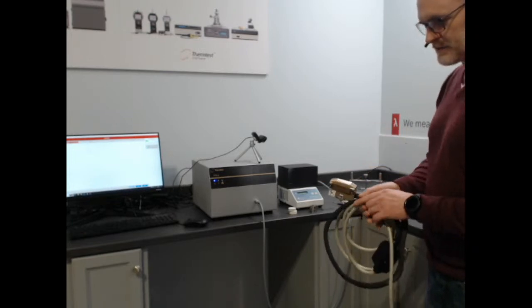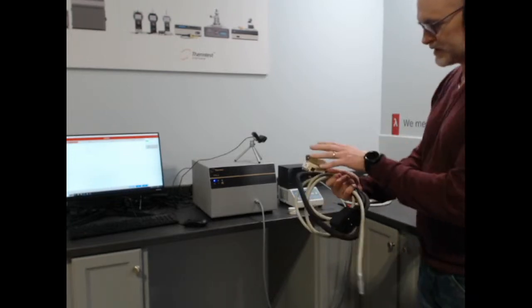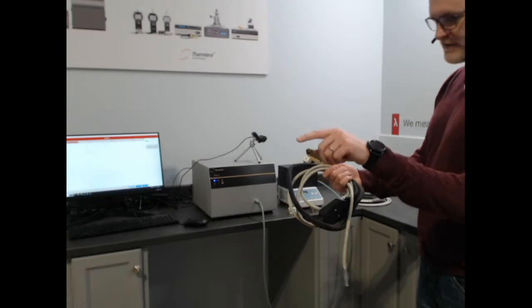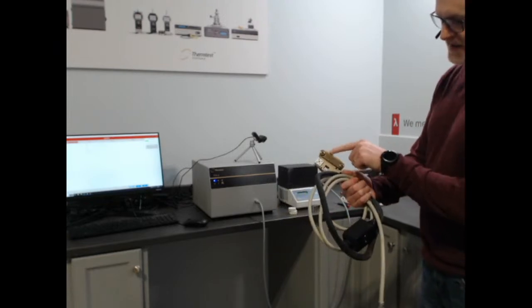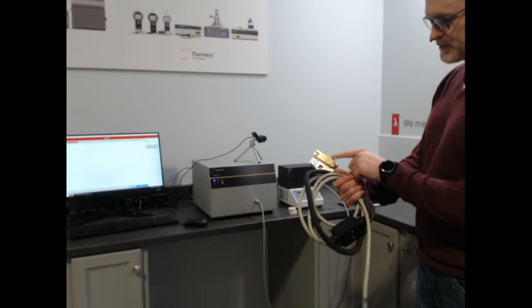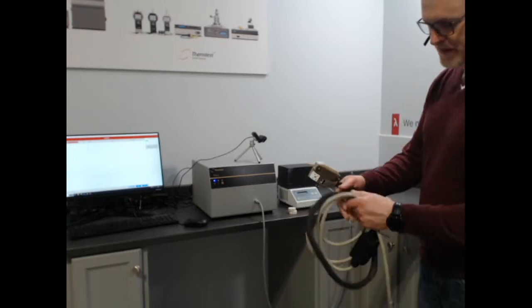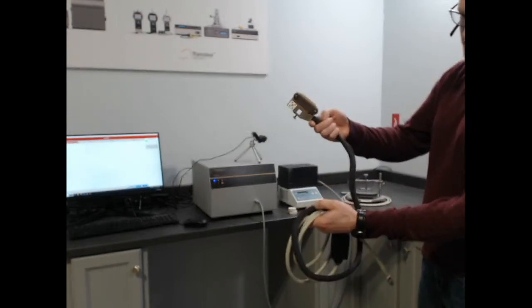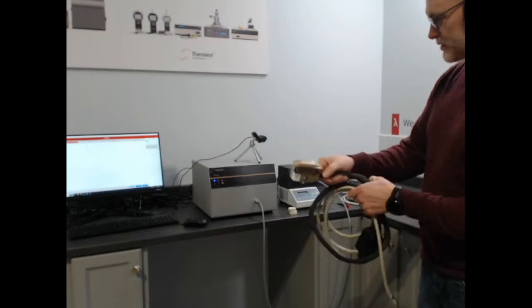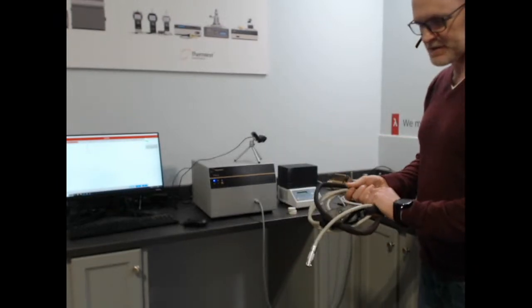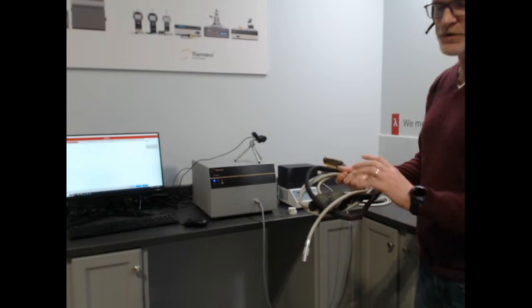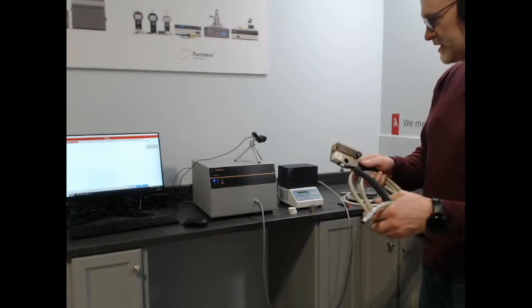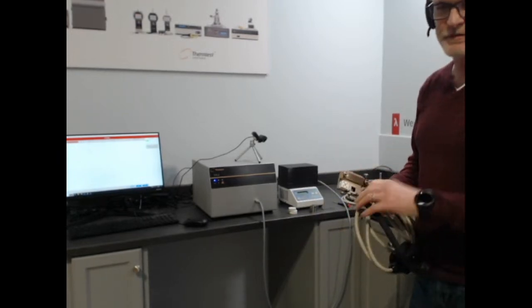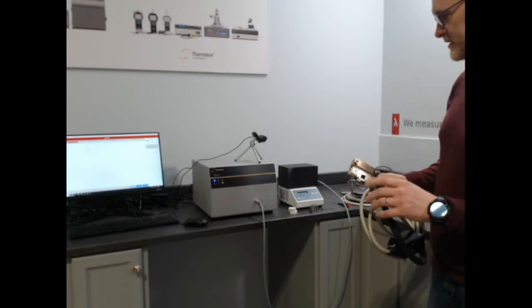We offer an arrangement of ovens that allow you to pass this cable through the oven, and your sensor is connected in much the same way as the room temperature one, just with a much wider temperature range. This is the high temperature portion of the cable. This stays inside the oven, of course, and so we can reach multiple options on measuring high temperature. So I thought I'd just share that. We didn't bring the oven over, which maybe we will another day.